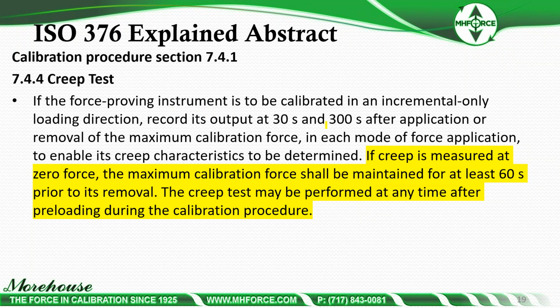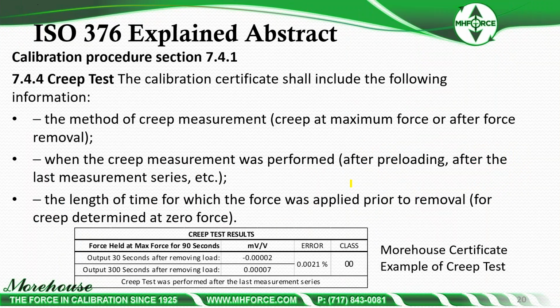In each mode of force application, to enable its creep characteristics to be determined, if creep is to be measured at 0 force, the maximum calibration force shall be maintained for at least 60 seconds prior to its removal. The creep test may be performed at any time after preloading during the calibration procedure. So we're going to get into that. It's a lot to process right now. We're going to get into that in a little more detail.